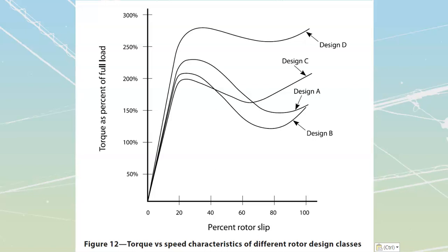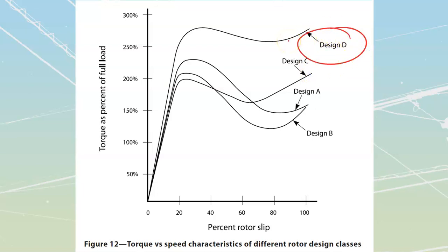All of these were off of a motor that had a regular three-phase stator. So all of them have the same types of stators, but it's the characteristics of the way the rotor itself is built that gives us design class A, B, C, or D. A and B were very similar. Design class C had a really high starting torque higher than its breakdown torque, but it still breaks down relatively low at about 200% torque. Design class D has a high starting torque and a high breakdown torque.